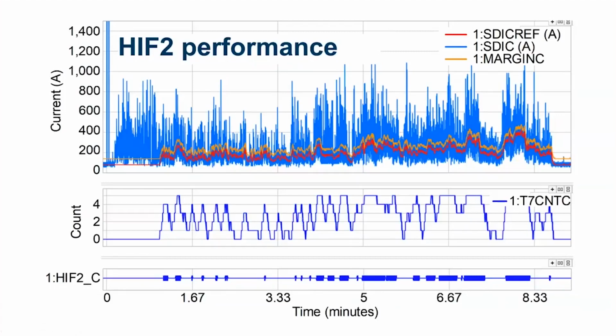So if you're using a 651R, you won't see these settings. These settings are set internally in the relay. The relay automatically uses these settings to compare the SDI with the reference. But yes, this is how the tripping bit asserts. Now we've looked at the tripping bit. Let's look at the alarming bit.